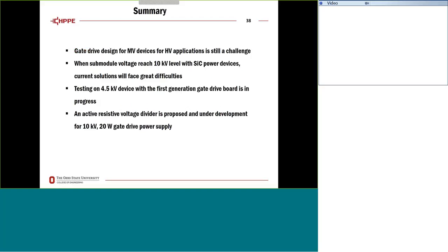To summarize today's presentation, if we want to use medium voltage devices for high voltage applications, we still have a long way to go; it's still very challenging. When using power harvesting from a 10 kV or above DC bus, existing solutions are not sufficient or are too complicated to utilize. So we've proposed our own solutions, and at the same time we're working on testing a 4.5 kV device to validate our gate drive designs, regular functions, and protection functions.